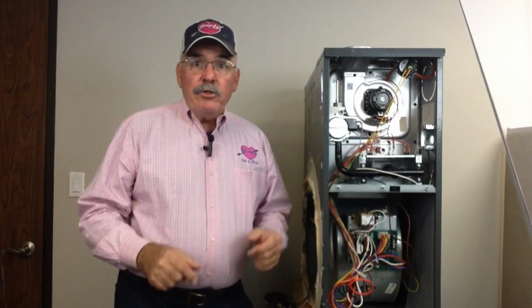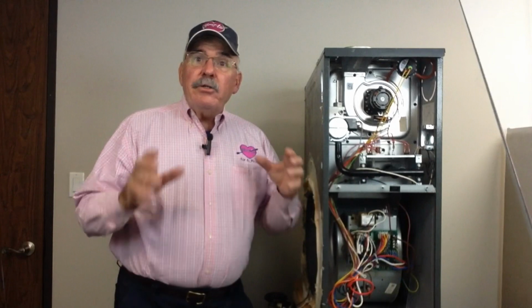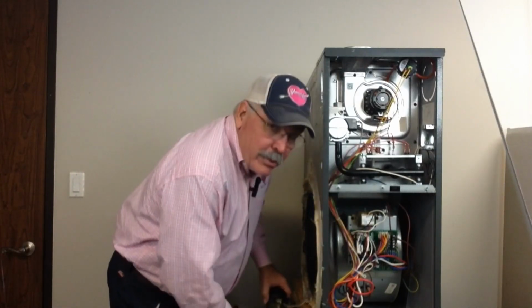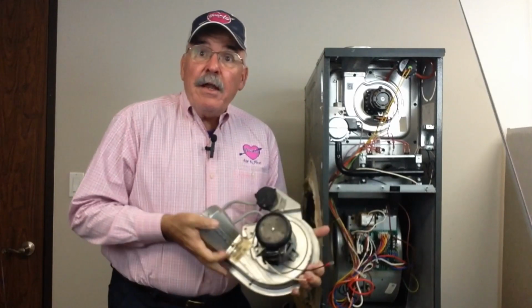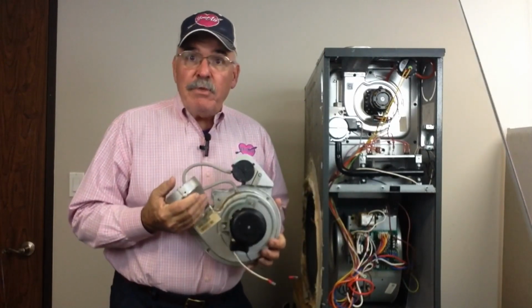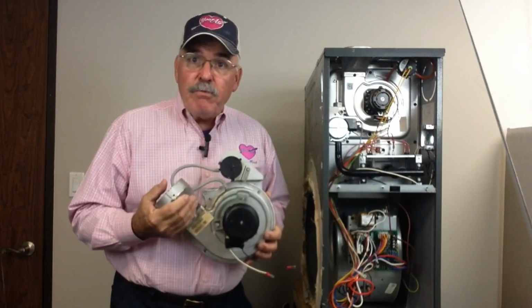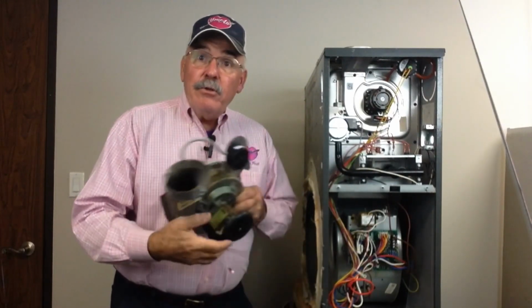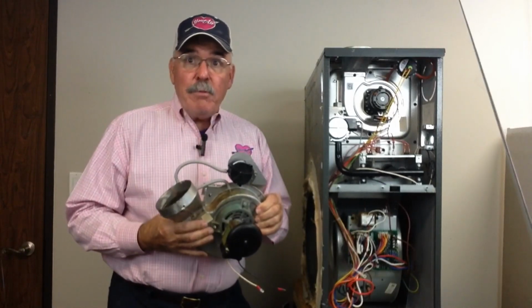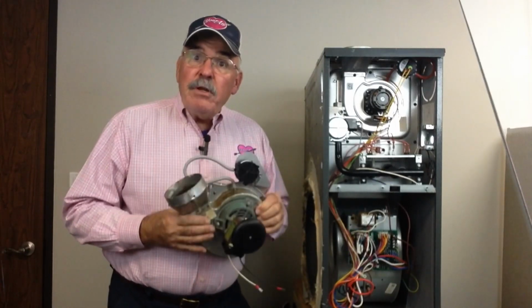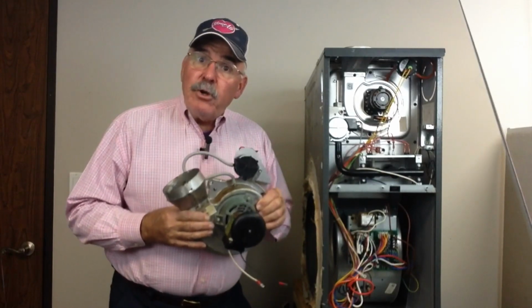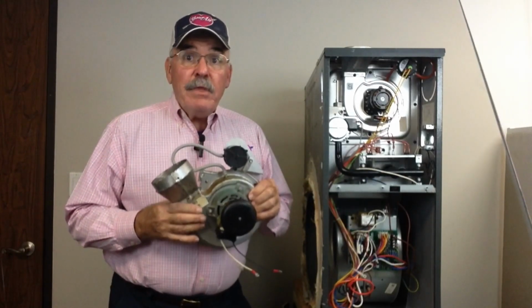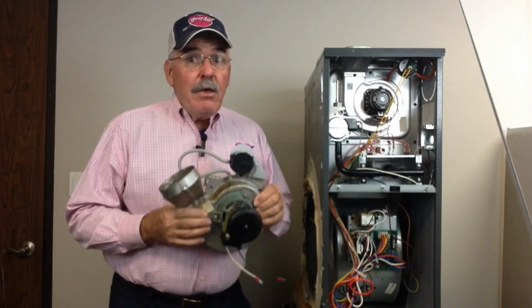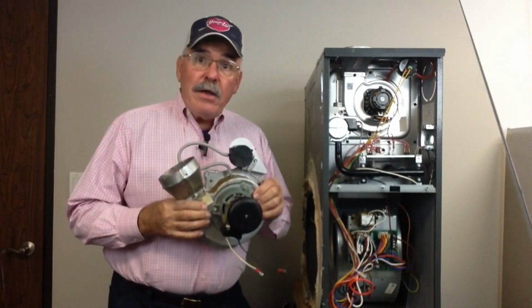And now we're ready to jump headlong into session 4 and discuss another very important part of your furnace that's critical for operation, and that's your inducer fan assembly. And it looks like this right here. Now the fan assembly is a very important safety device in your furnace. It consists of the inducer fan blades, which are located in here, the inducer fan motor, which is right here, and the casing, which holds it in place. This assembly is the first in a vital series of safety devices designed to make sure your furnace is going to operate correctly. If this component doesn't operate properly, your furnace is not going to turn on and you're not going to have any heat.